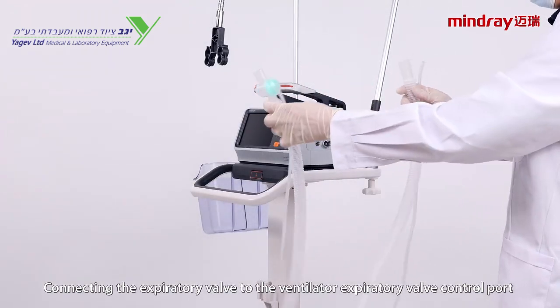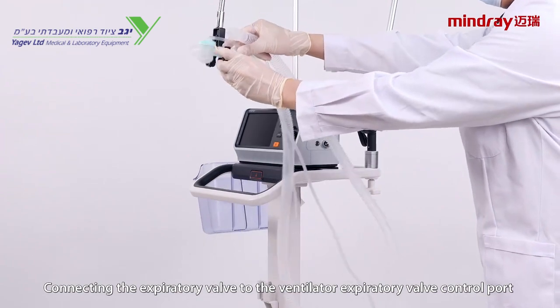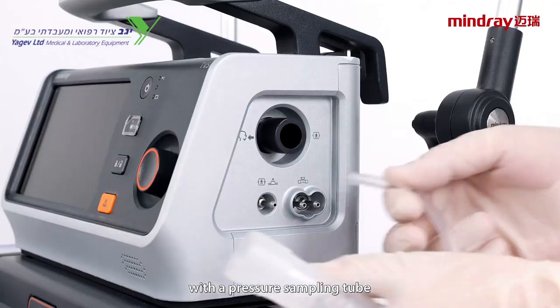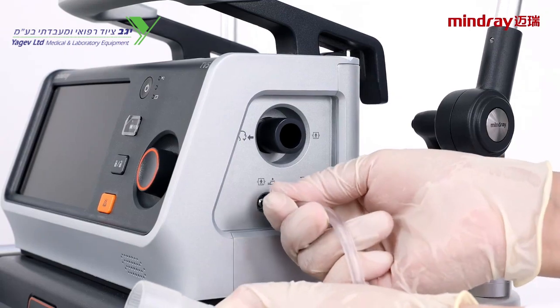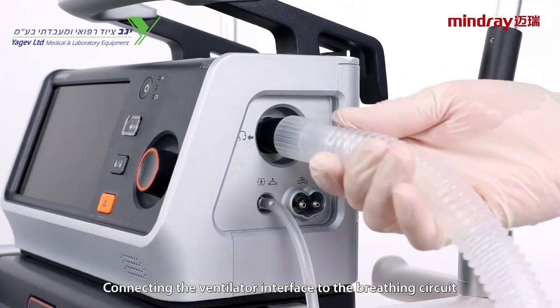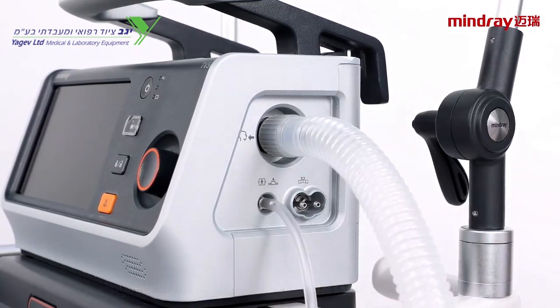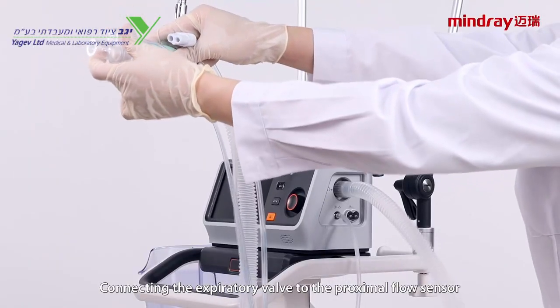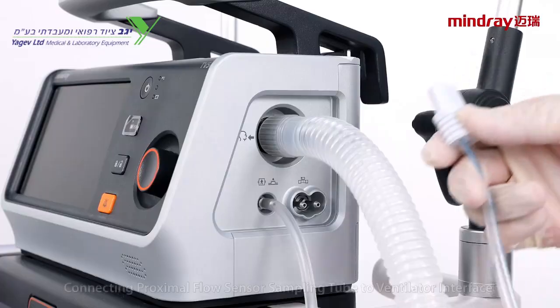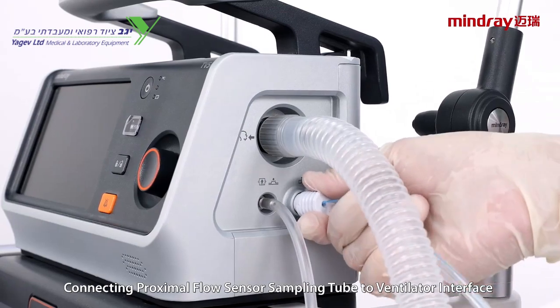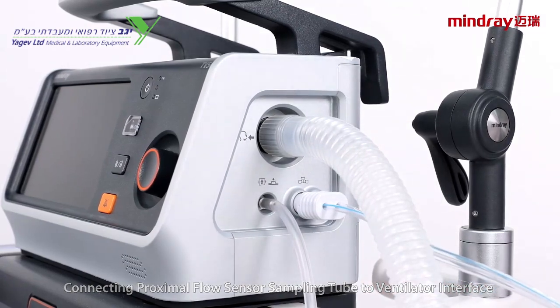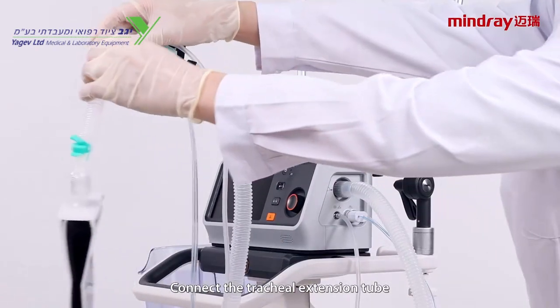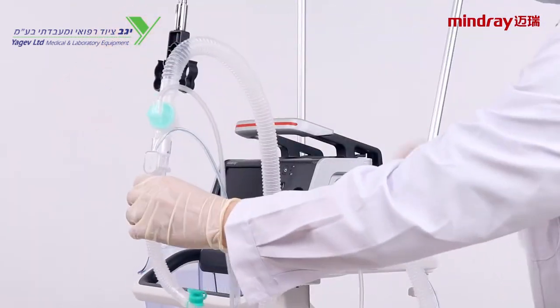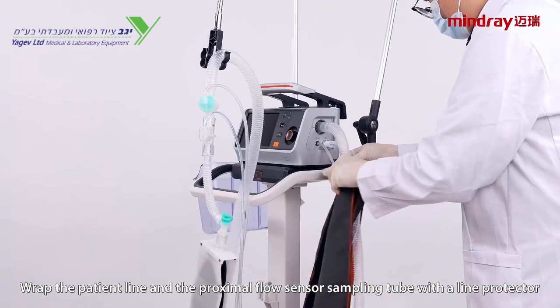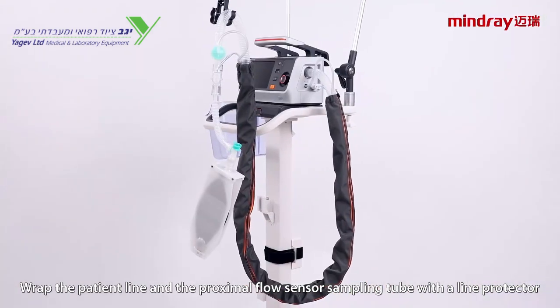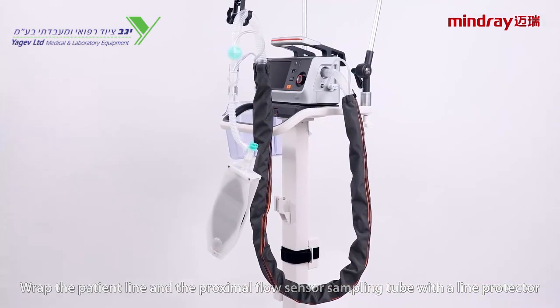Connecting the expiratory valve to the ventilator expiratory valve control port with a pressure sampling tube. Connecting the ventilator interface to the breathing circuit. Connecting the expiratory valve to the proximal flow sensor. Connecting proximal flow sensor sampling tube to ventilator interface. Connect the tracheal extension tube. Wrap the patient line and the proximal flow sensor sampling tube with a line protector.